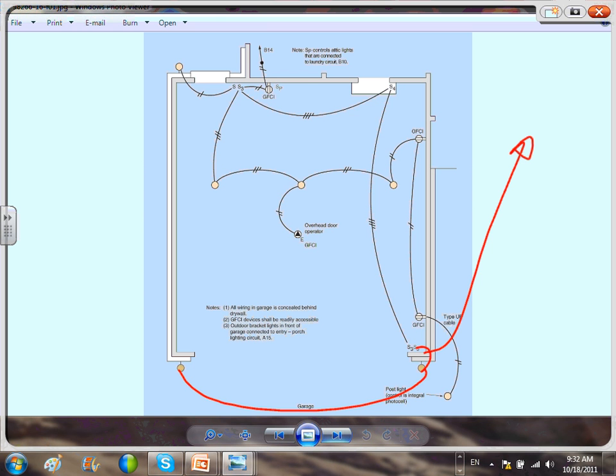When we do wiring, remember two things. Every receptacle needs a hot and a neutral, and every light needs a neutral and a switched hot. Every switch needs a neutral, a hot to feed it, and a hot to go out of it. Think of any switch: it needs a hot and a switched hot or switch leg, and a neutral, 3 wires. If you have a 3-way switch, you also need 2 travelers and a neutral and another hot or switched hot, 4. So the way I always remember: a light needs 2 wires, a receptacle needs 2 wires, a 3-way switch needs 4 wires.